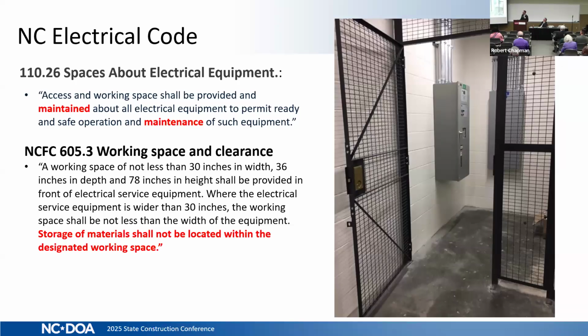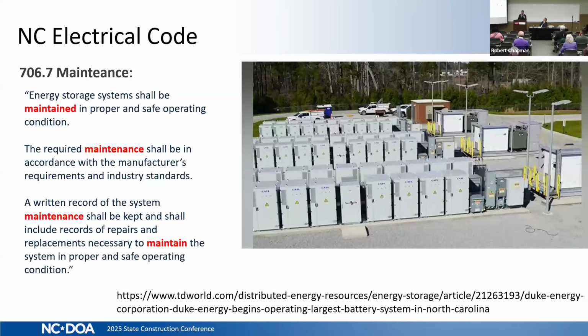So we see here that the NEC, that's pretty much a violation in quite a lot of facilities that you go to. But in this case, we want to make sure also if we do the caging that it complies with what the NEC requires for access. And I believe this is a Duke Energy storage facility. We know that batteries need maintenance. And then there are new battery technologies coming out all the time. So each one of those may have different maintenance requirements as specified by the manufacturer. And we just want to highlight that those need to be complied with.